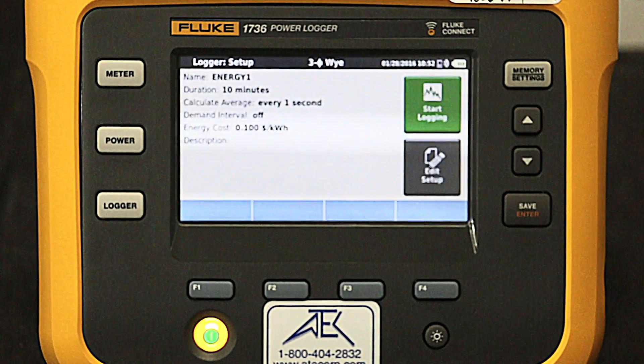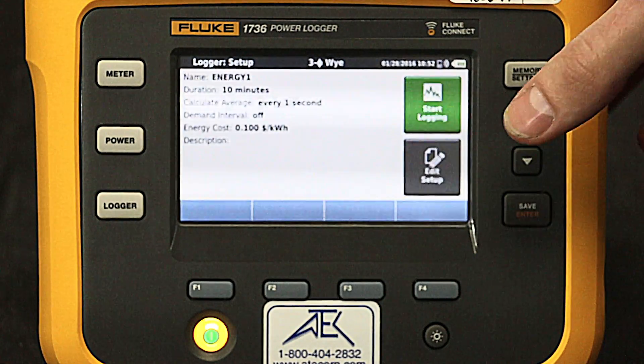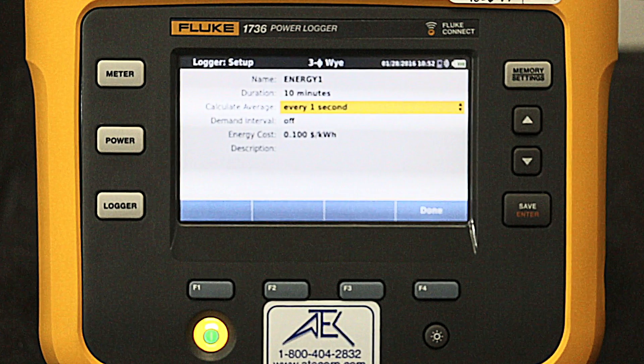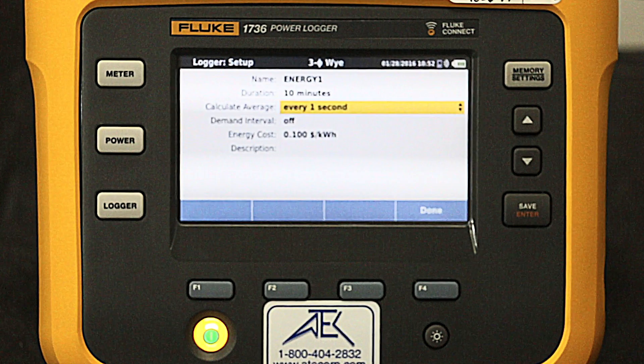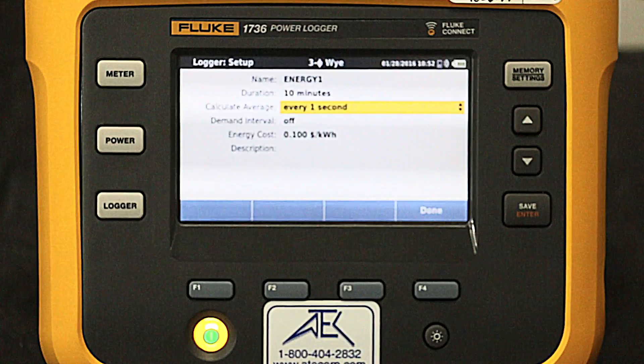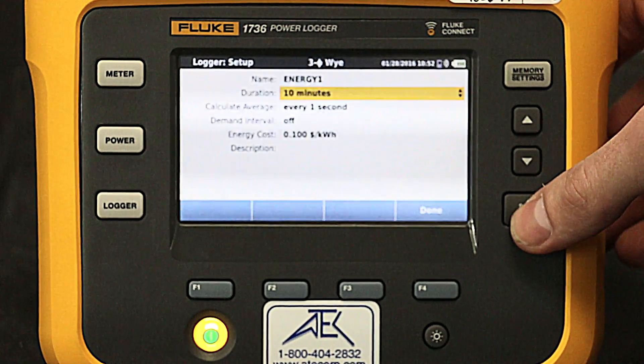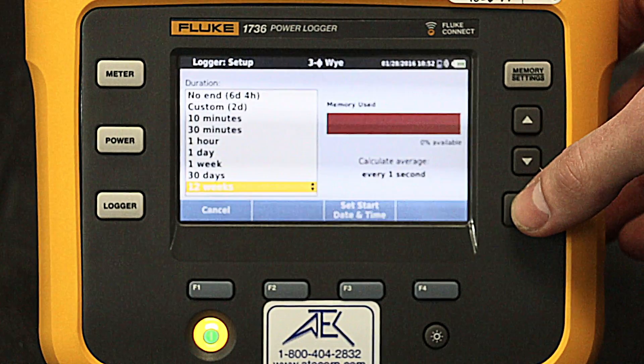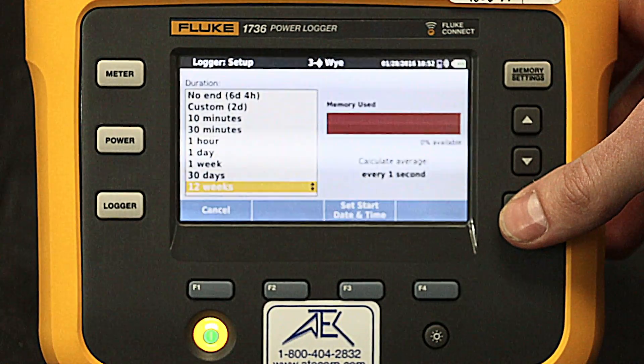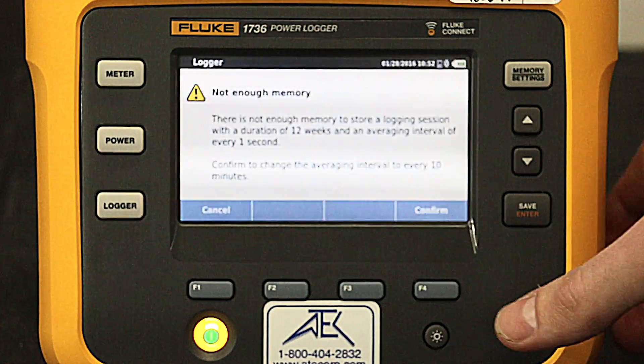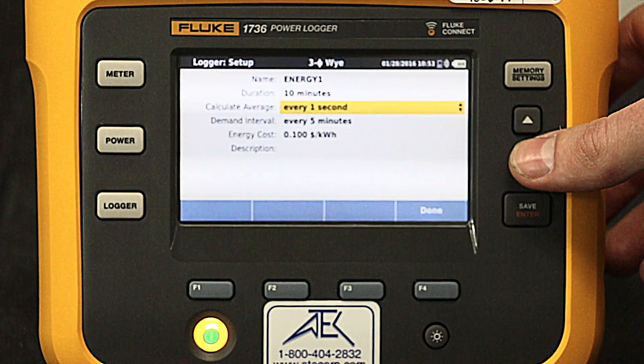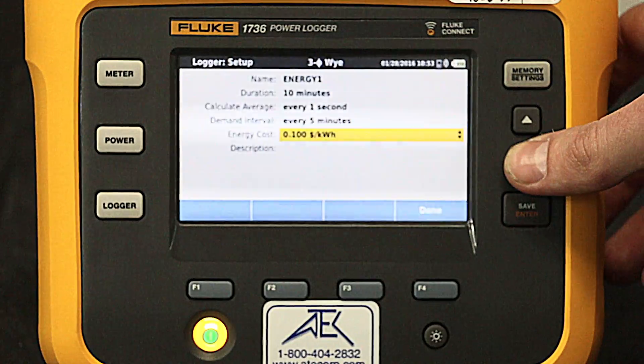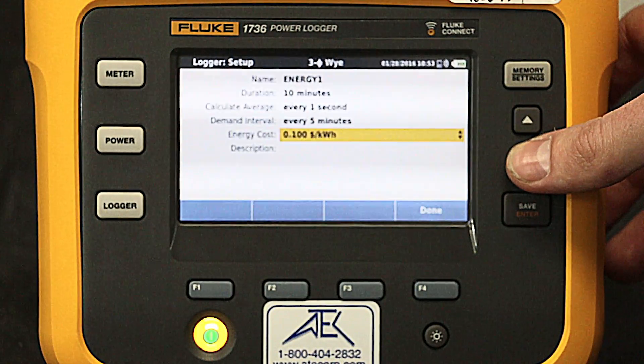Now let's set up the logger. By clicking Edit Setup, we can see the Energy 1 log is set up to record the energy data every second for a duration of 10 minutes. If we wanted to change that, we could by scrolling down through the presets. Note that we do not have enough memory to run a 12-week log every second. For this demonstration, we will record every second for a demand interval of 5 minutes.